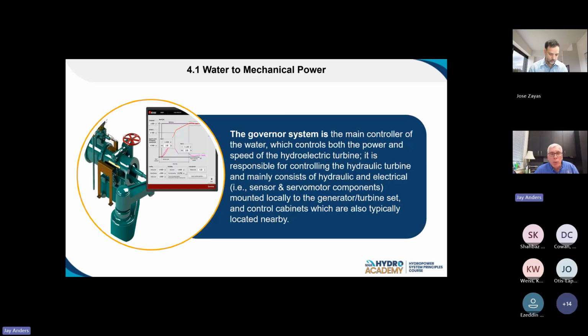Well, the first piece of equipment I want to talk about is the governor. And this is not the guy that sits in the capital of your state and tells people what to do, doing things good or bad depending on how you view it. The governor for us is the primary mechanism that controls the position of the wicket gates. The wicket gates - think of them as a valve. These wicket gates control how much water is let into our turbine, and depending on how much water goes into our turbine, that controls how many kilowatts we put on the system. It's interesting - realize the governor is also thought of as a speed control device.